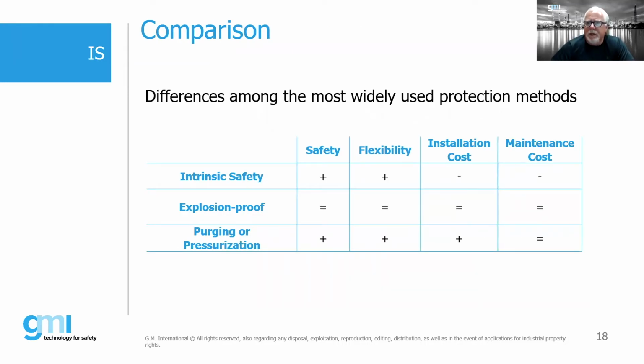When we talk about the protection concepts, there are certainly some advantages and disadvantages with intrinsic safety versus flame-proof, explosion-proof, purging, or pressurizing. If we look at flame-proof or explosion-proof as kind of the median, intrinsic safety has an extremely high safety record. It is very flexible. Also, the installation cost can be less, and the maintenance cost can be less. I hate speaking in generalities because there are always exceptions to the rules, but in general, intrinsic safety, when applied properly, can be very cost effective. Purging and pressurizing is also very safe and very flexible. There is sometimes a significant installation cost because we have to deal with ductwork to provide air to a panel, and maintenance cost is about the same as flame-proof. These are generalities. It doesn't apply for all installations, but they are some of the most common.